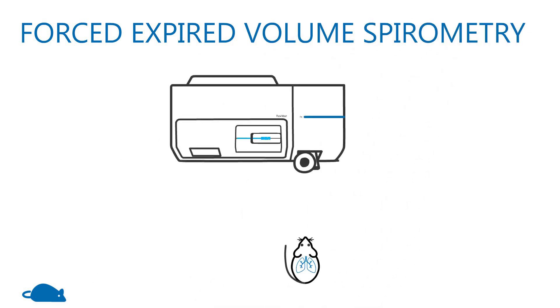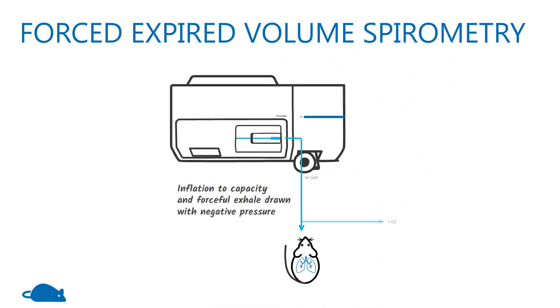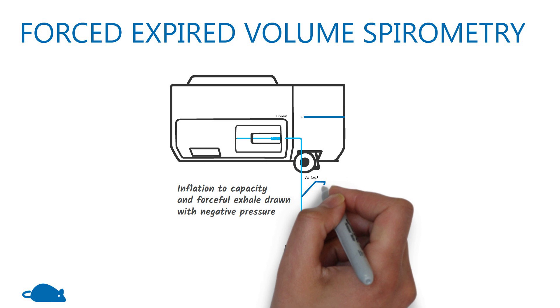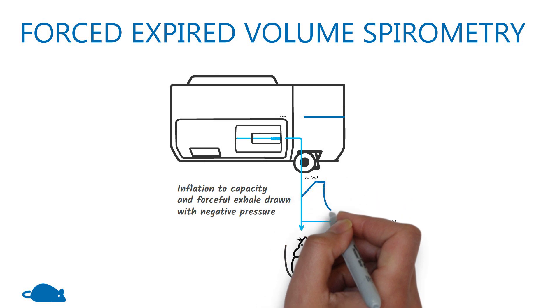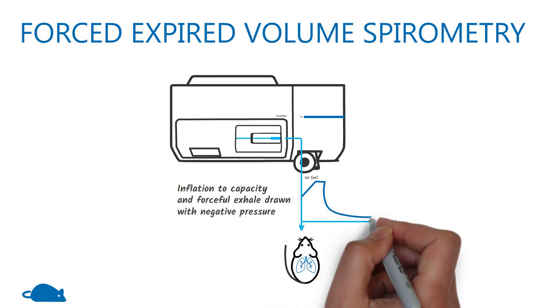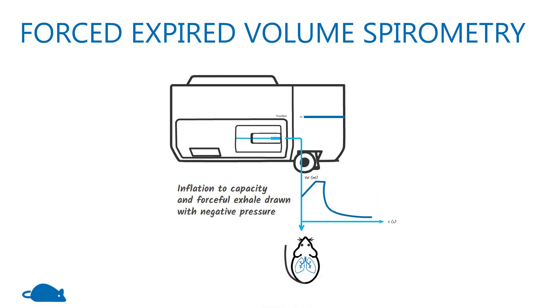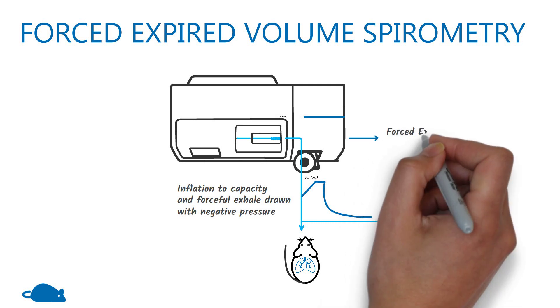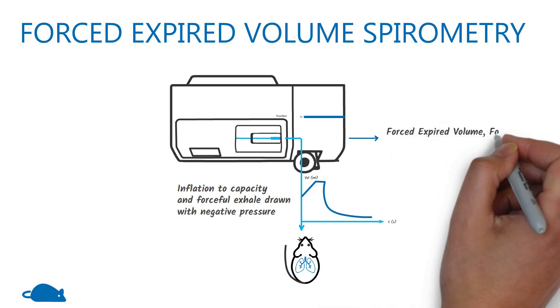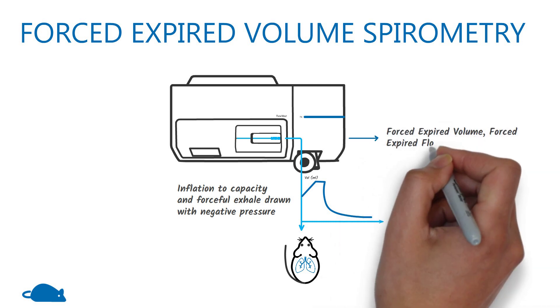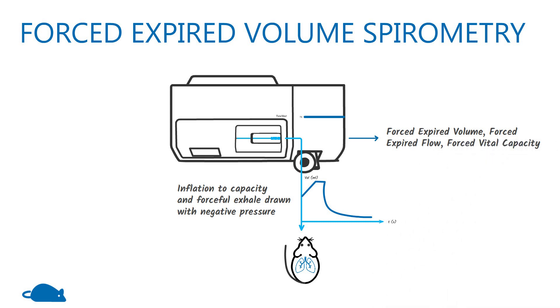In the forced-expired volume measurement, the lungs are recruited to total lung capacity and then a forced expiration is elicited with exposure to a negative pressure. This allows the flexi-vent to calculate spirometry-like measures such as forced-expired volume, forced-expired flow, and forced vital capacity.